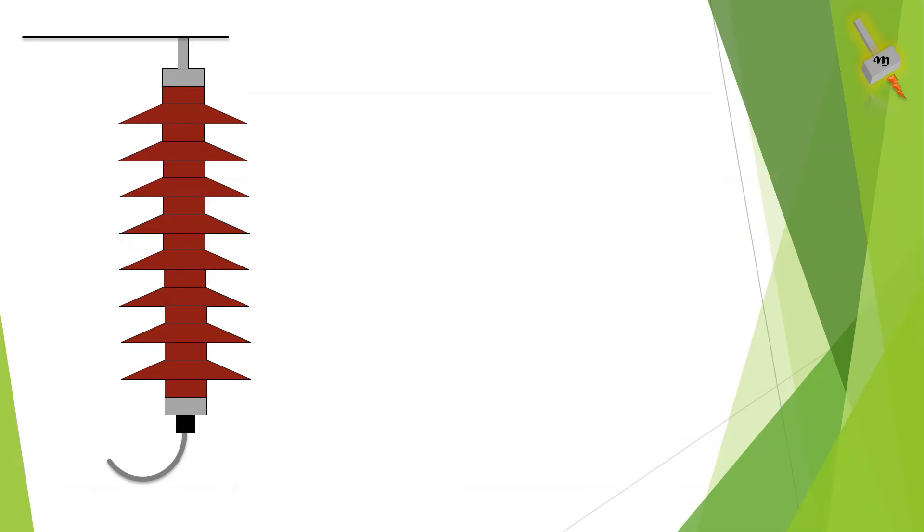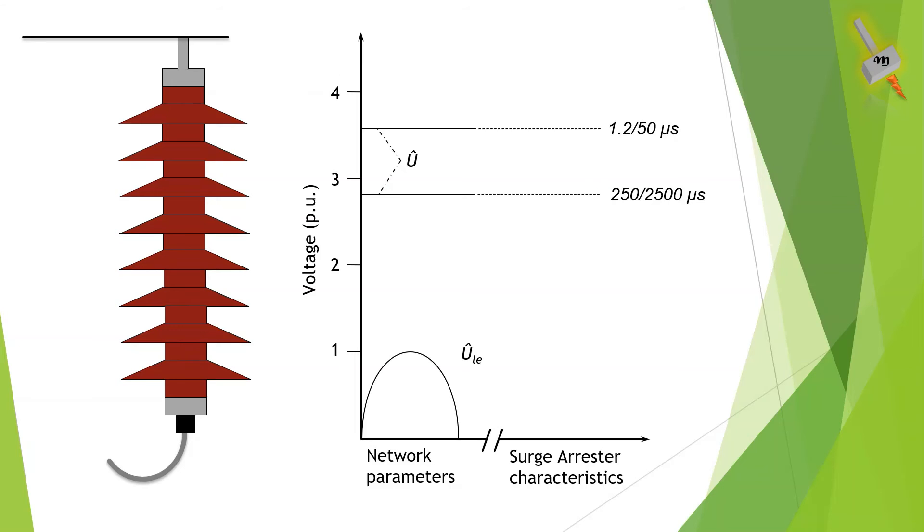Now let's see what happens to a lightning arrester before and after a surge event. This is a line to earth voltage of a three phase system. These are switching and lightning insulation levels of that three phase system. This is the rated voltage of the surge arrester which is derived as earth fault factor times the line to earth voltage.